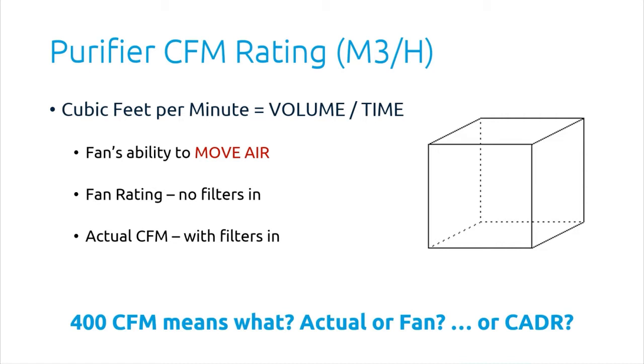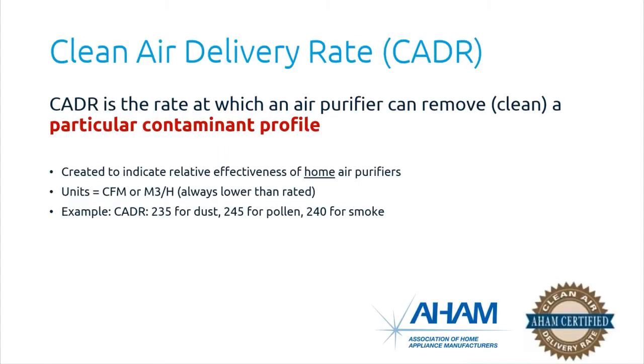And with no filters and no resistance anywhere, it moves 400 CFM, let's say. But when you put filters in, that same unit might only now move 250 CFM. So what are you actually reading when an air purifier manufacturer publishes the spec that says 400 CFM? You should know whether it's the fan rating or the actual CFM through the unit. Or maybe it's the CADR. The clean air delivery rate is very similar to CFM, actual CFM.